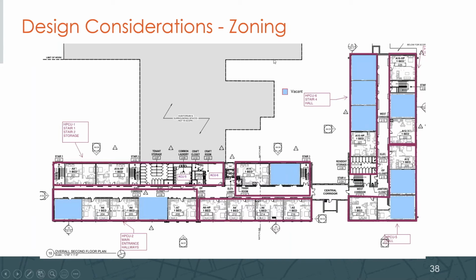The problem is, in these zones, some also included stairs. And the stairs, according to historic, could not be insulated on the interior. They also had double swing doors, which are very air leaky. And so those zones stay cool as opposed to the apartments. So if only one zone, say this one zone here, needed heating, the refrigerant in this entire zone stays charged in the line. So it's running throughout apartments, and it is enough to keep all of these apartments at least 68 degrees, even if their thermostats are off, if this one zone is calling for heat. And that is in design conditions.